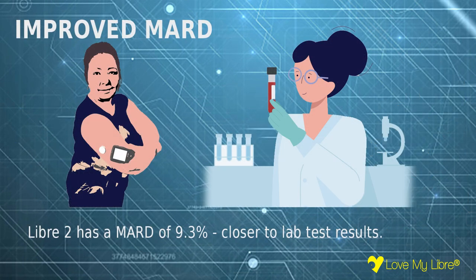The MARD, which stands for mean absolute relative difference, is now 9.3%, down from 11.4% for Libre 1. This means that Libre 2 is more accurate when compared to a blood test carried out in a lab, and it should improve the accuracy of that estimated HbA1c figure on LibreLink.